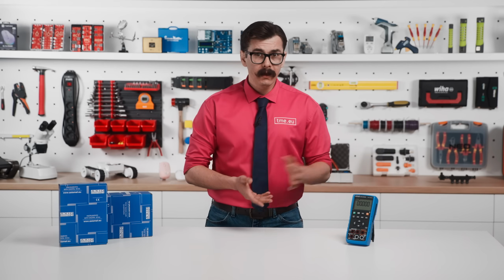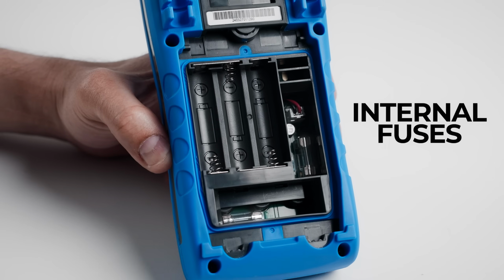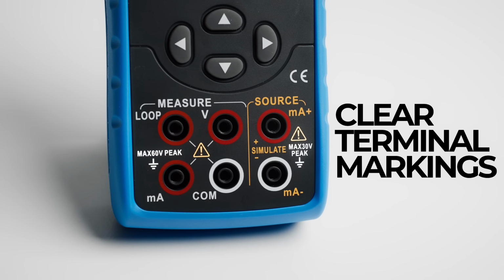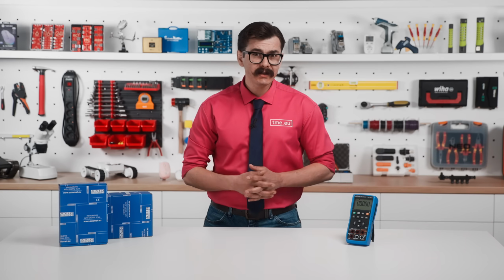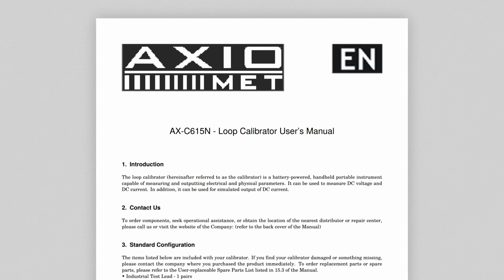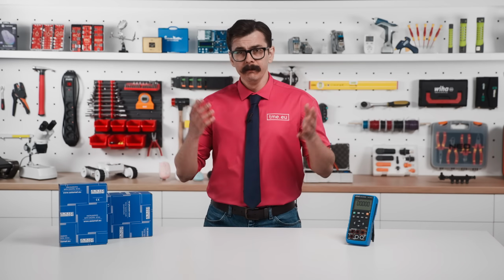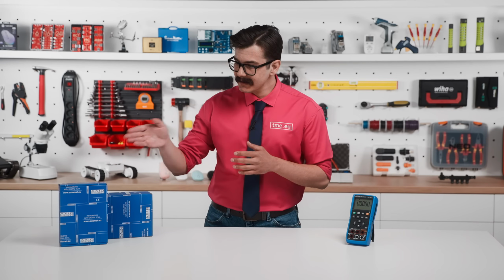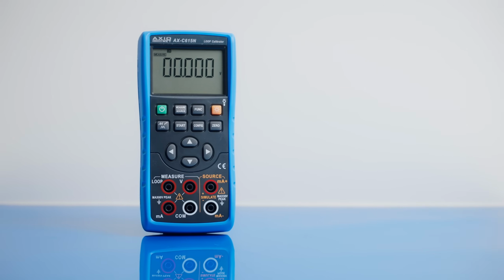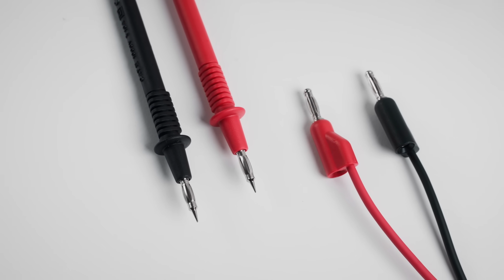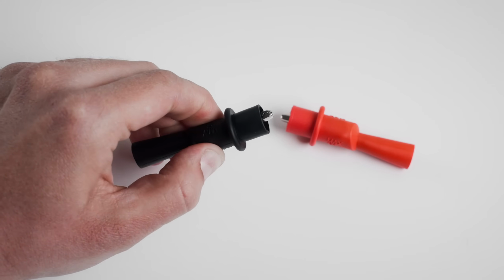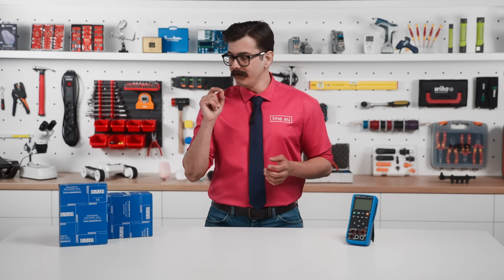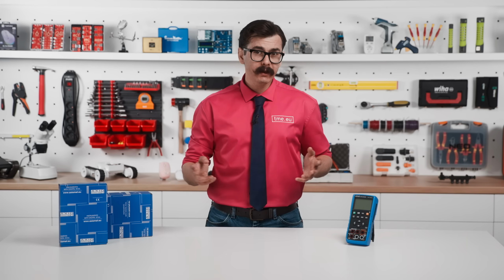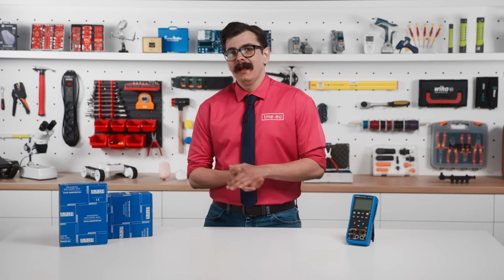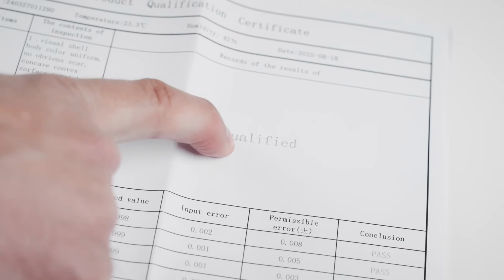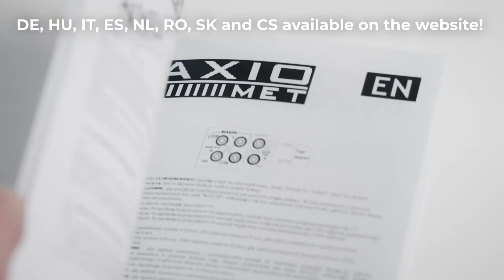In terms of safety, you get standard protective features such as the internal fuse and clear terminal markings to avoid exceeding the rated voltage. Although it is designed for typical industrial and workshop environments, make sure you read the user manual and operate the device according to those instructions. Those are included in the box, but not only. Inside of the box we also have the loop calibrator itself, one pair of industrial test leads rated for 1000 volts, a set of alligator clips because an extra hand is always helpful, not one, not two, but 4 fuses because, well, I guess Axiomet knows how things sometimes turn out. A key for unlocking the back panel, a qualification certificate, the user manual in English and Polish, and batteries are not included.